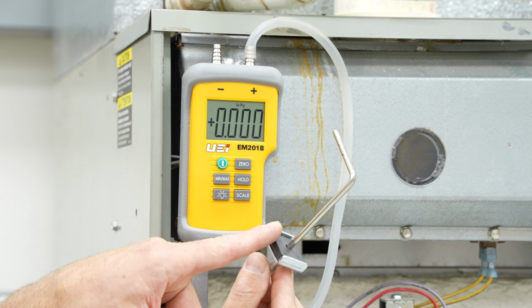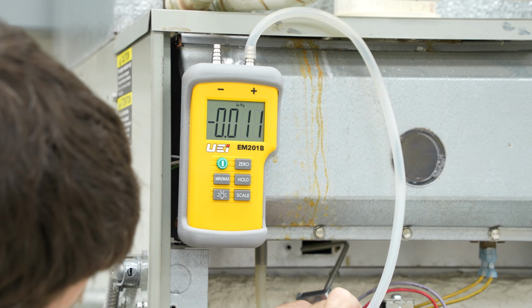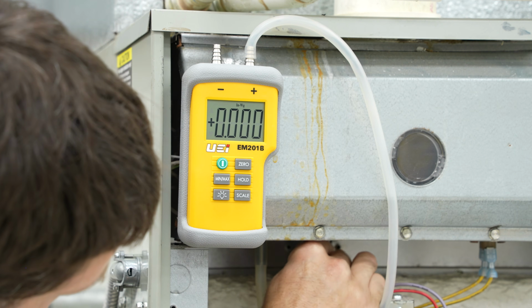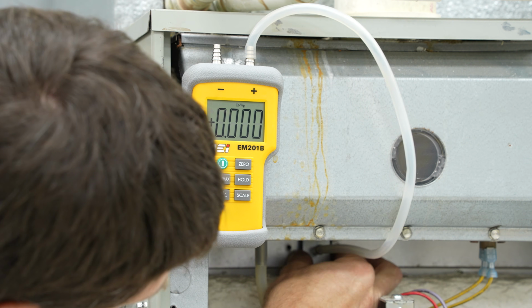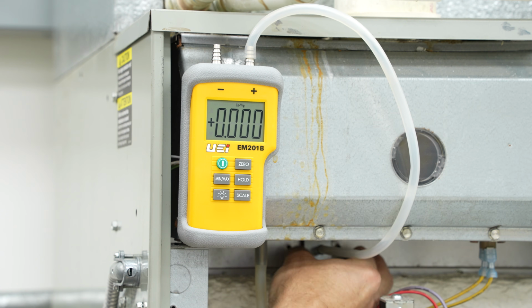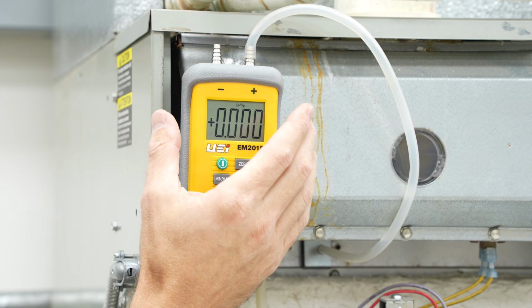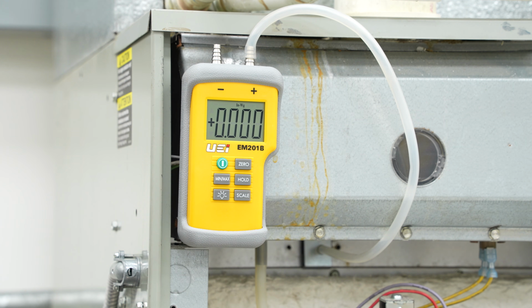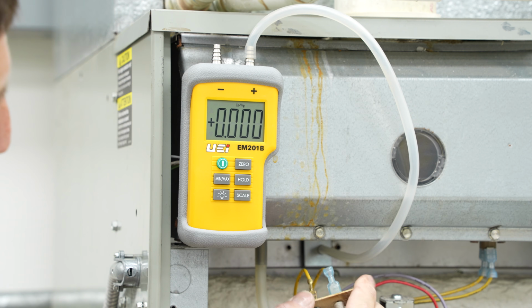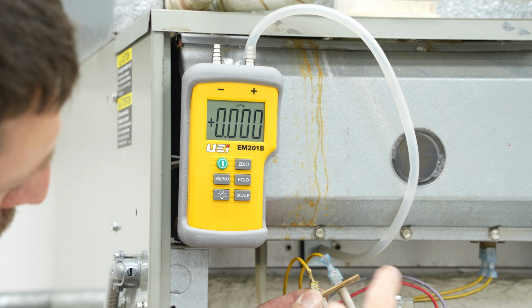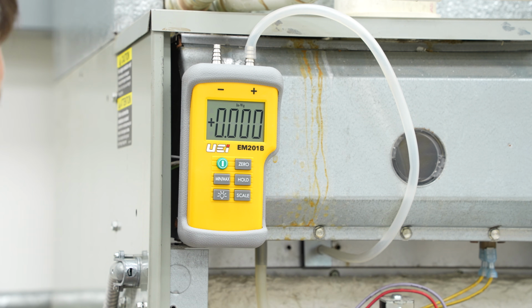We're going to take our static pressure tip attached to our digital water column manometer. We're going to put this in and face it downwards, and cover over the hole. You could always use tin tape to cover the hole if needed, and make sure you zero out your water column manometer. And the other thing is, with this switch, make sure that it doesn't short out on any metal, because we're going to turn the power back on in order to measure this.